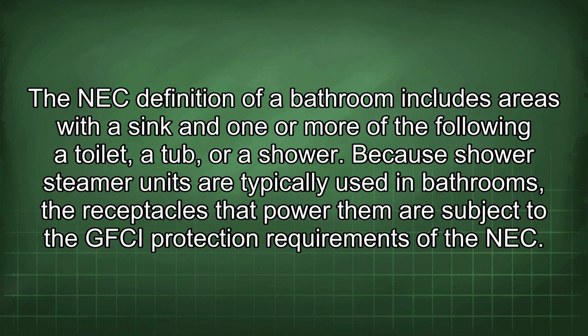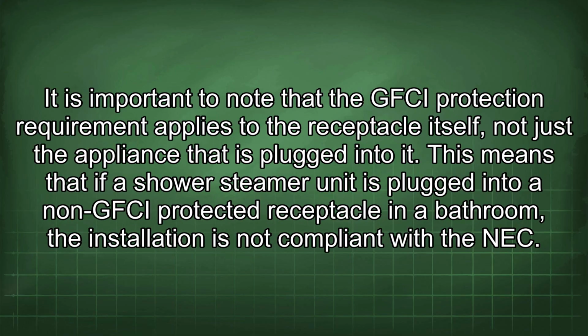Because shower steamer units are typically used in bathrooms, the receptacles that power them are subject to the GFCI protection requirements of the NEC. It is important to note that the GFCI protection requirement applies to the receptacle itself, not just the appliance that is plugged into it. This means that if a shower steamer unit is plugged into a non-GFCI protected receptacle in a bathroom, the installation is not compliant with the NEC.